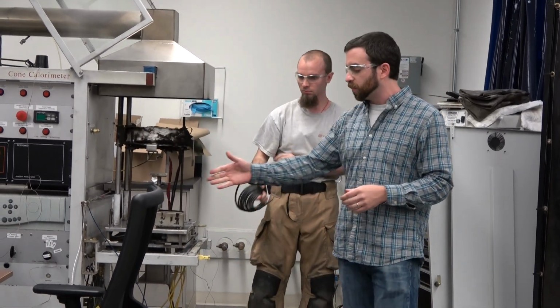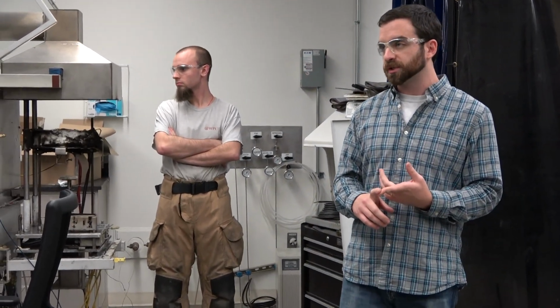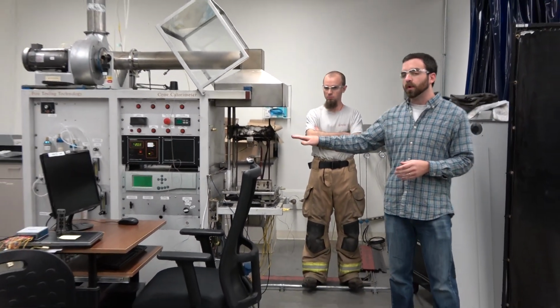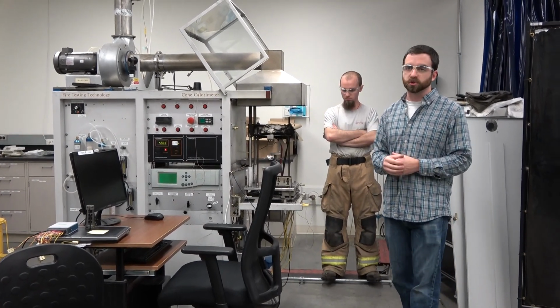And so when we have an ignition, we'll measure soot production, CO2 production, we'll measure your mass loss rate, and most importantly, we're going to measure your oxygen concentration. So the basis of this calorimeter is what we call oxygen depletion calorimetry. For every 1 gram of oxygen consumed, we produce 13.1 kilojoules of energy. So independent of what material you're burning, we can tell the power output simply by measuring that O2 concentration.